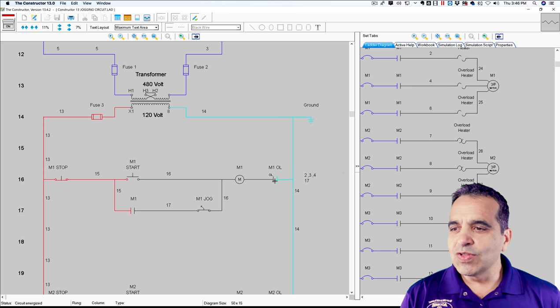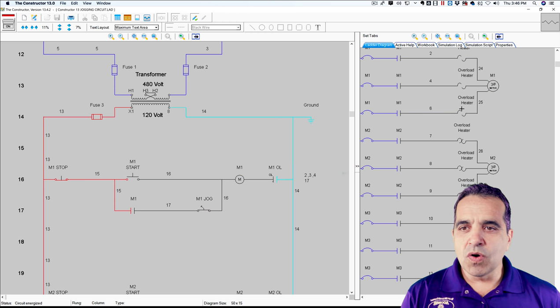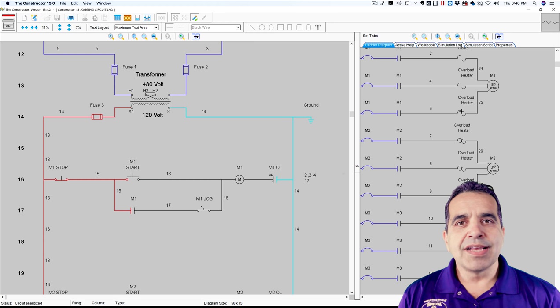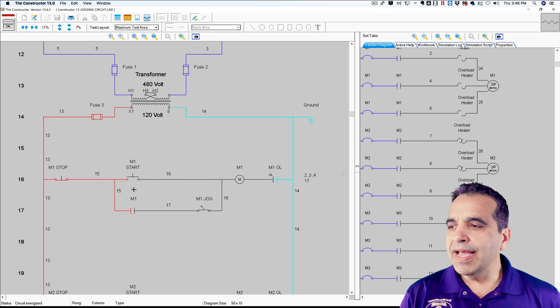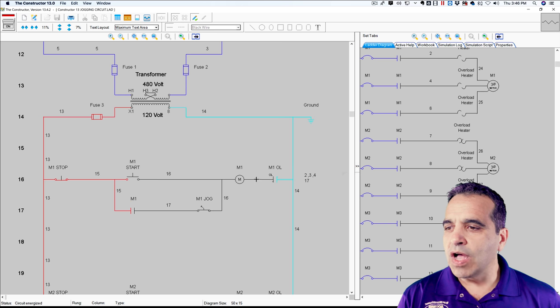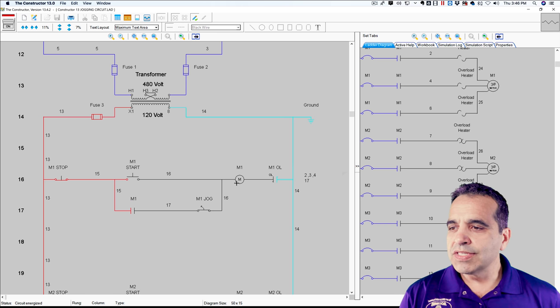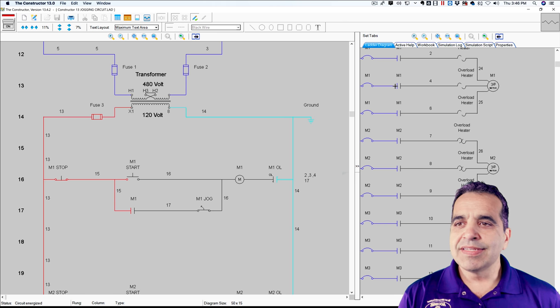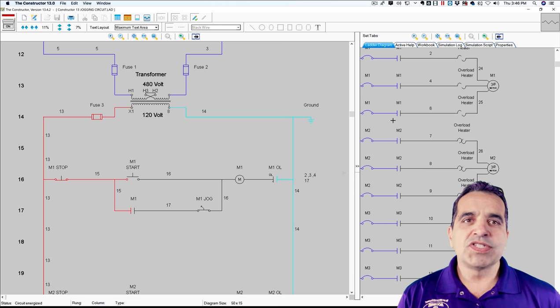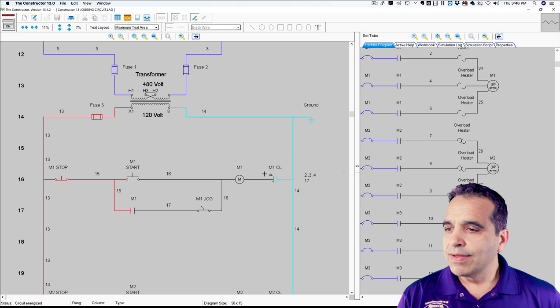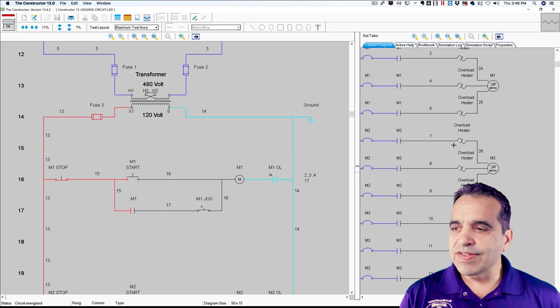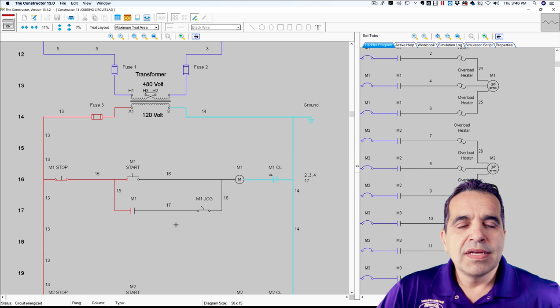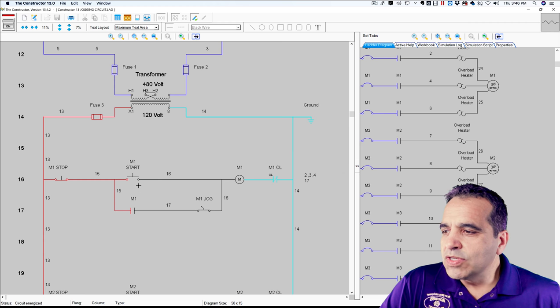If we lose our overload, our overload opened over here and the heaters opened and turned the motor off. We lost our neutral to this control circuit, which de-energized the coil, de-energized the contactor, which de-energized the motor. So let me reset my overload. My overload is reset. So now what is this switch here? Let me show you.